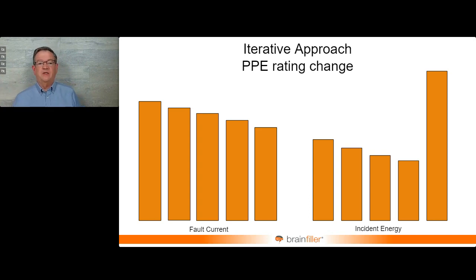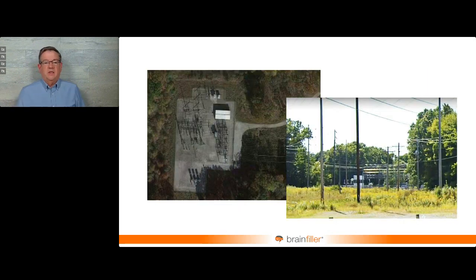So this is not a perfect answer, but what it does is define a range of source currents where your PPE would be sufficient, and then shows, okay, how low can this go before we start to have some problems. The configuration, this goes back to my utility days, when I was responsible for planning a transmission substation years back. I was in the planning department for a year before I went to the short circuit studies group. And when this substation went online, the fault currents in the area jumped by about 20%.